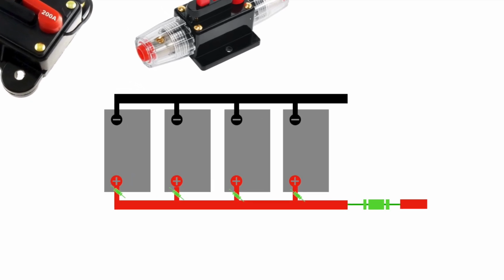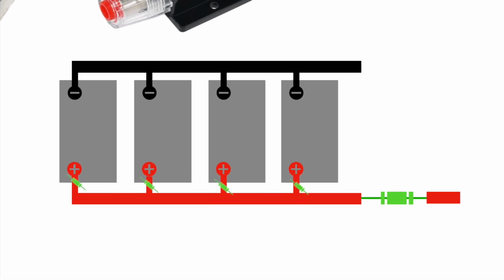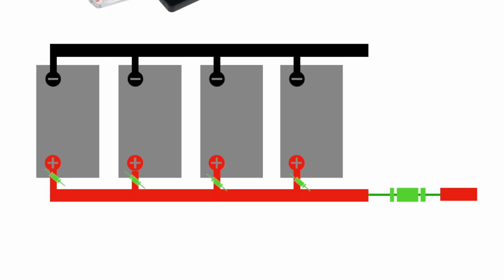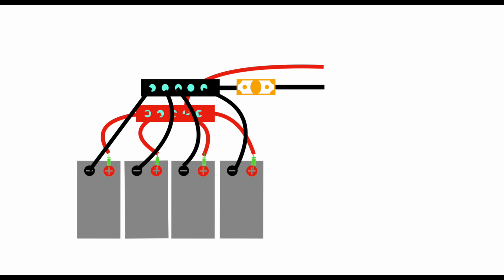We also prefer fuses. We've seen circuit breakers that have not tripped out and nearly caused fires. So we tend to use fuses. And of course, if you're using individual conductors or wires of the same length to keep all your batteries in balance, then it's more likely that you will want to protect each individual conductor rather than this conductor here only. Putting the fuses in this position also helps to protect the BMS inside the batteries.